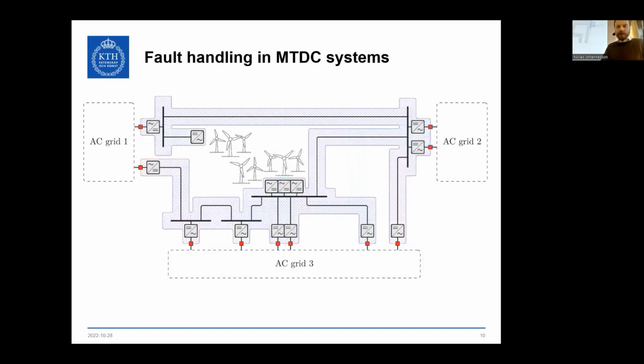However, if we start connecting them into a multi-terminal system, if you get a DC fault, all of the converters are going to contribute to the fault current, which means you would need to trip all the AC breakers of all the converters. This might be acceptable for small examples, but not for larger ones. If each converter at the bottom is 1 gigawatt, for instance, you could lose 6 gigawatts in a single failure, which is more than most networks could handle — maybe only China or something.